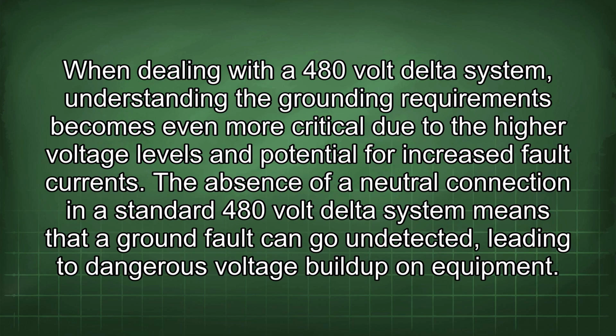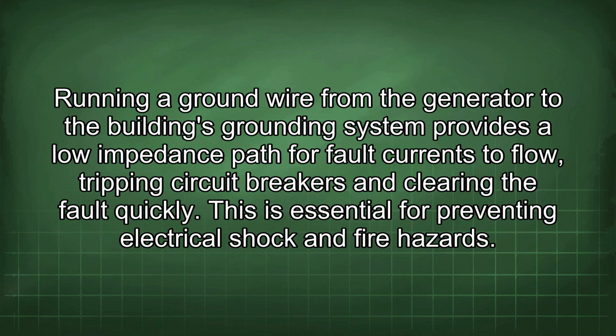When dealing with a 480-volt delta system, understanding the grounding requirements becomes even more critical due to the higher voltage levels and potential for increased fault currents. The absence of a neutral connection in a standard 480-volt delta system means that a ground fault can go undetected, leading to dangerous voltage buildup on equipment. Running a ground wire from the generator to the building's grounding system provides a low impedance path for fault currents to flow, tripping circuit breakers and clearing the fault quickly. This is essential for preventing electrical shock and fire hazards.